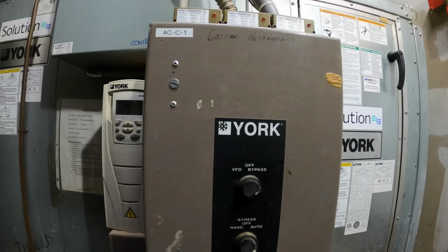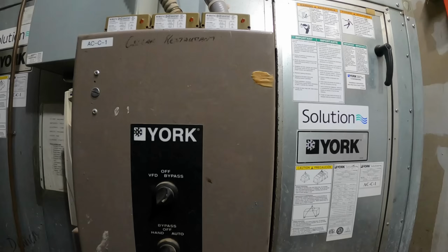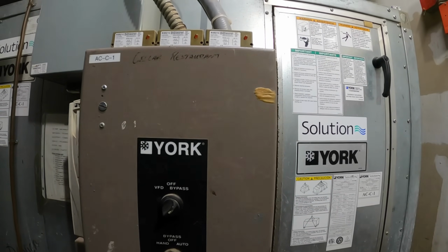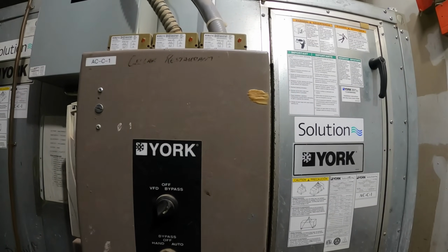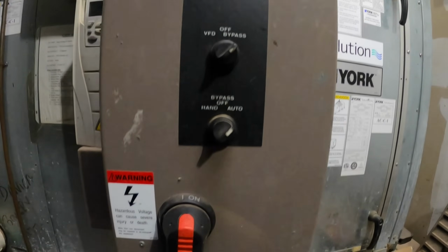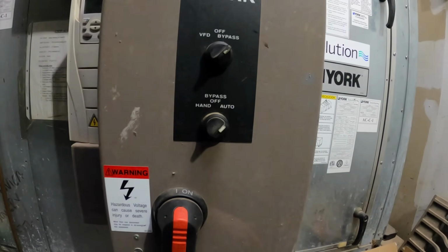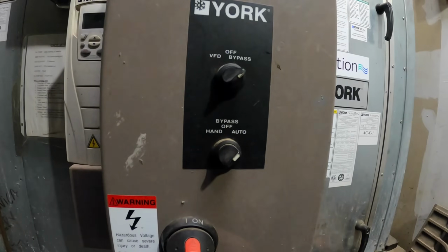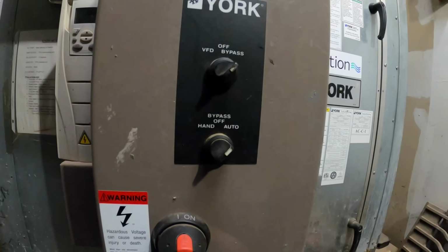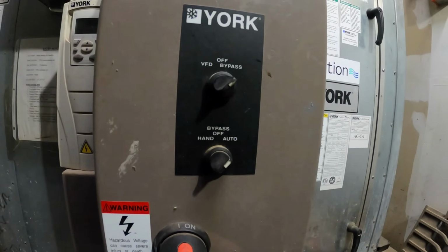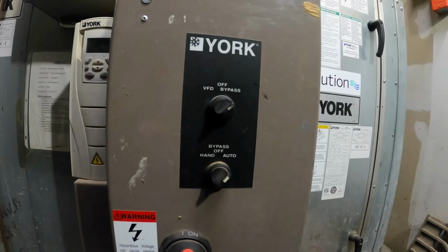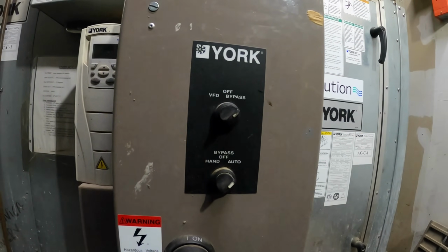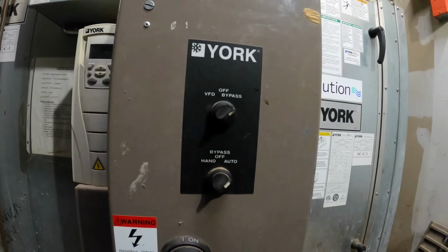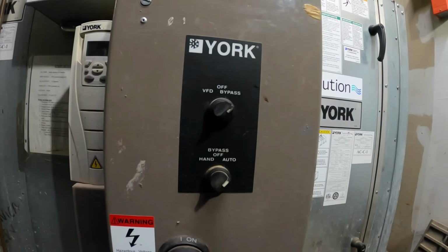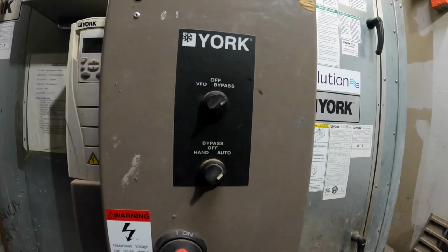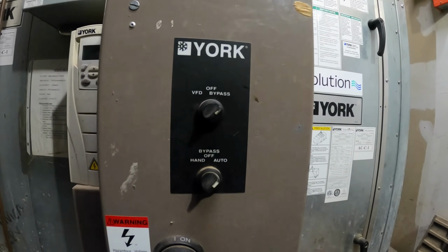It's not like any traditional method. I didn't really have anyone teaching me anything traditional here. I just kind of know electricity and controls and have a good background in technical things and HVAC, so I kind of just freestyle it. But one thing told me, hey, check that fire cable, and I was checking when the power was off or anything like that. I was just seeing if there was power across. There wasn't, so I checked continuity and there was no continuity. Turned all the power on, then I checked between the two and I had 120 volts across, so it wasn't closed - it was an open circuit.